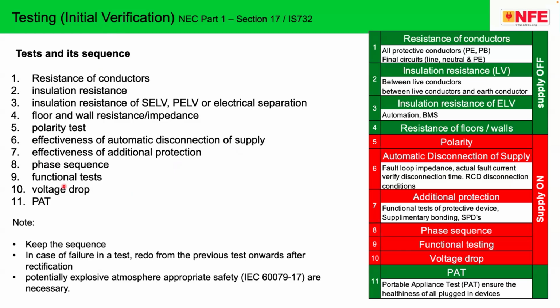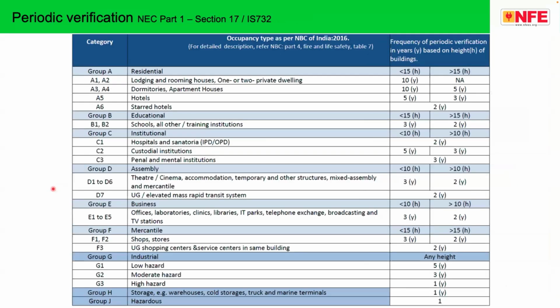Once you carry out the test, you can identify the defect, and the contractor must rectify the defect and put the supply in such a way that before using the electricity, you are sure that you have a perfect electrical installation. Then you have to maintain it and you have to do periodic verification. The National Electrical Code gave some tables where the recommended years between periodic verification are included.